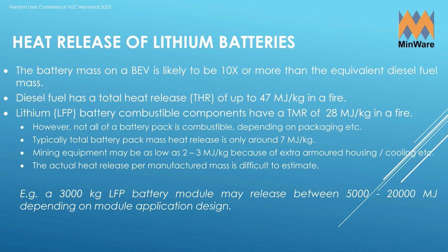That said, if your battery is 10 times the mass of your diesel, that 7 megajoules becomes quite a significant heat load. So the battery mass of lithium batteries, because they're so much heavier in total, puts out a very similar amount of heat to an equivalent diesel load. We're not getting any more or any less heat coming off a burning battery than off a tank full of diesel fuel.